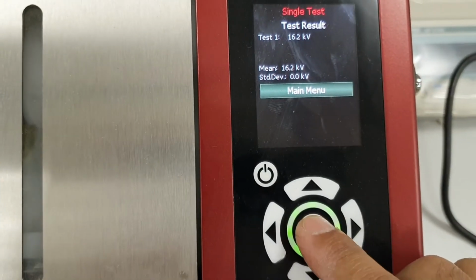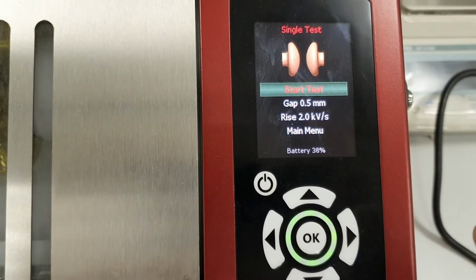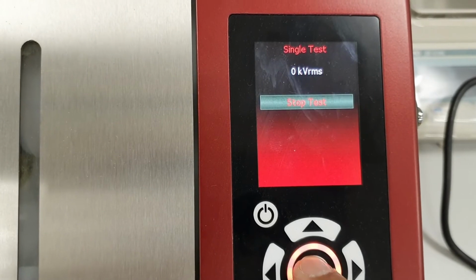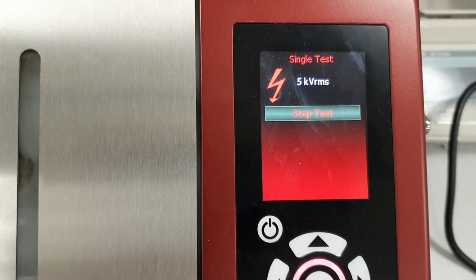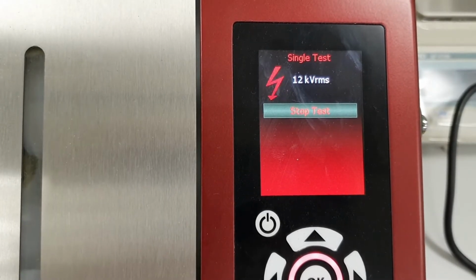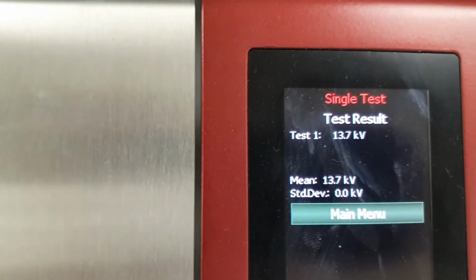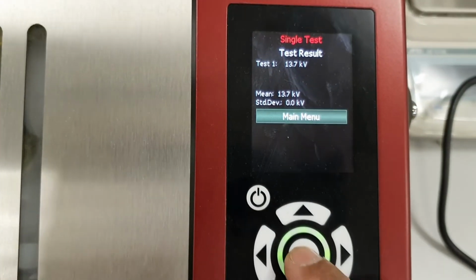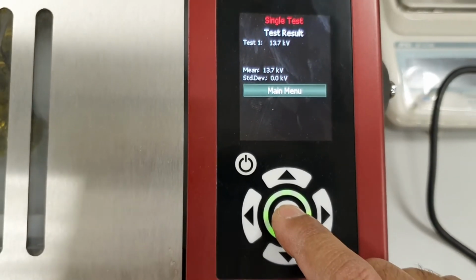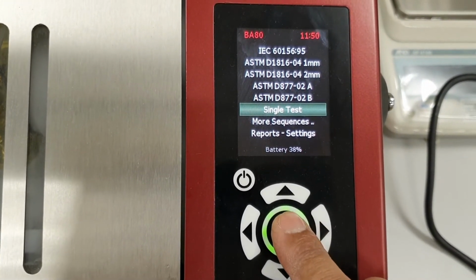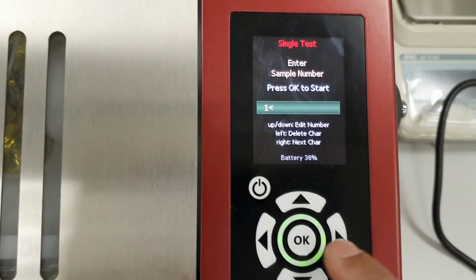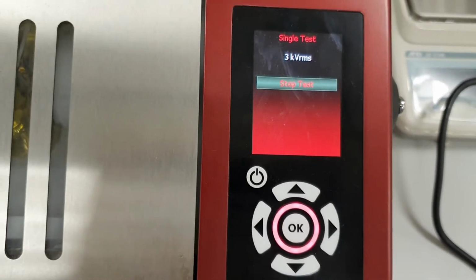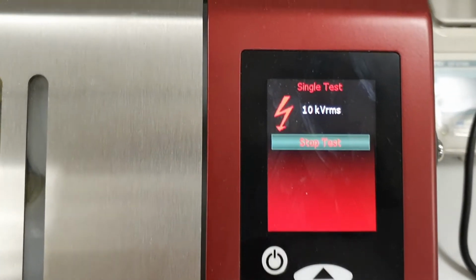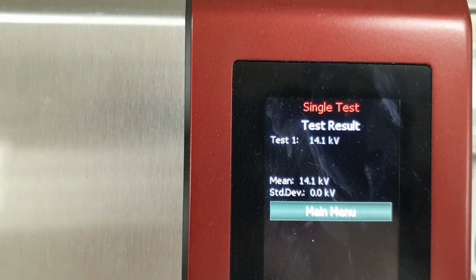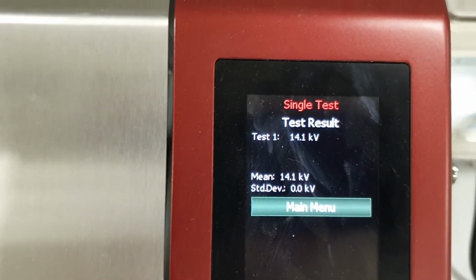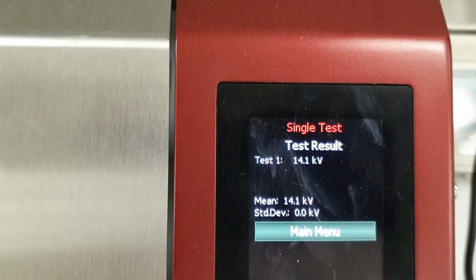Then we go again to the main menu and repeat 3 times for each gap. Second, press 1 and then start increasing. It's all RMS. So this second reading is 13.7. We need to repeat once more to get a good average of all three. Press OK, then single test, then press start again. The voltage is increasing. So 14 kV. We have three readings: 13 point something, then 16.2, 14.1. We'll take the average of all the three readings.